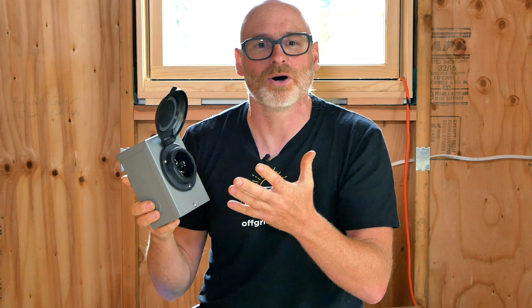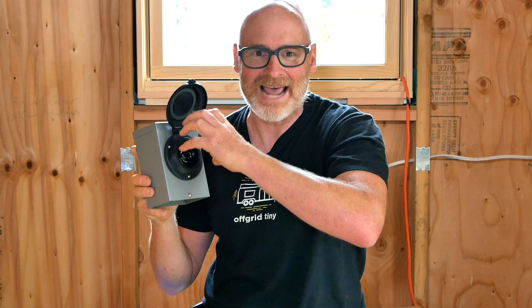The way RVs are wired, even if they're wired with a 240 volt box like this, is they're always coming to 120 volt loads on the inside of the panel. That's important because if you have a 240 volt load on the inside of a panel and you plug in a 120 volt adapter that has an internal jumper in it, that jumper just connected these 2 hot legs into a single 120 volt leg. And if those are now going into the opposite legs of your bus bar, and you're trying to feed a 240 volt appliance off that, you've basically taken electricity that's meant to oscillate back and forth like this, and forced it right into both sides.